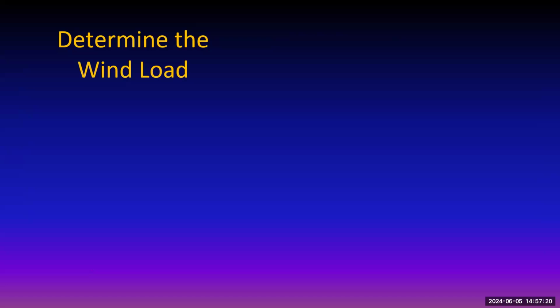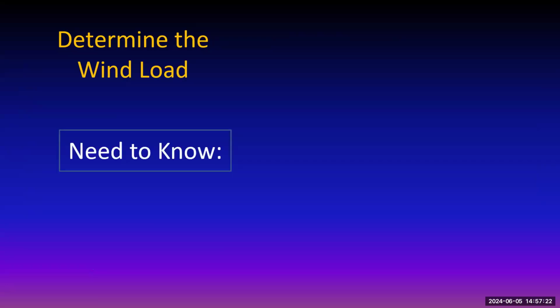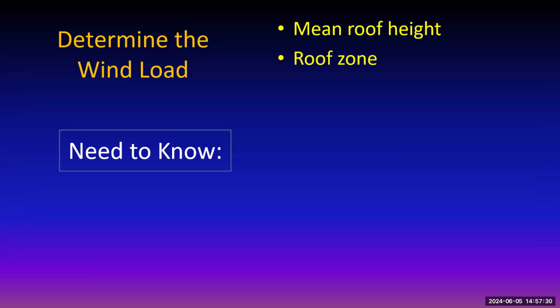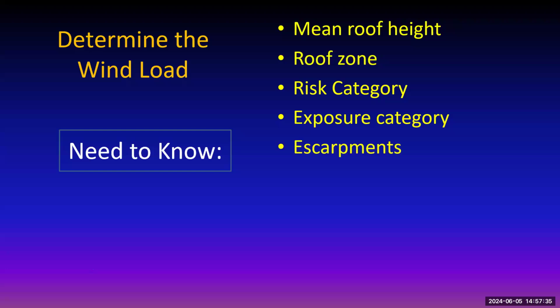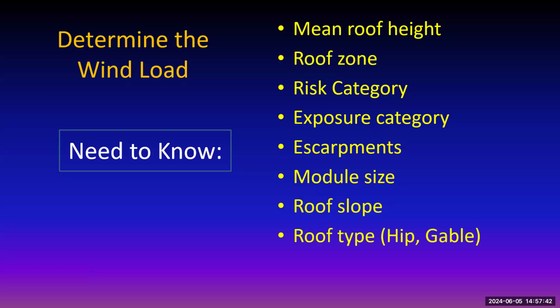First thing we have to determine is the wind load. That's fun. These are the things you need to know. You need to know the mean roof height. You need to know the roof zone. You need to know the risk category. You need to know the exposure category. You need to know the escarpment, whether it's on a hill or not. You need to know the size of the module. You need to know the slope of the roof. You need to know the type of the roof. And you need to know how fast the wind is going to blow. That's all you need to know in order to do a wind load calculation. All right, sounds simple, doesn't it?